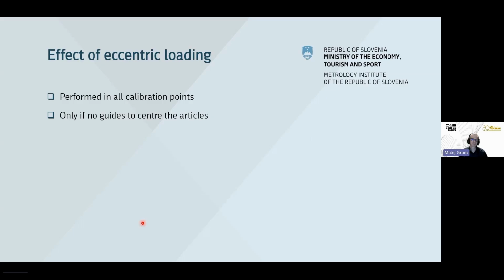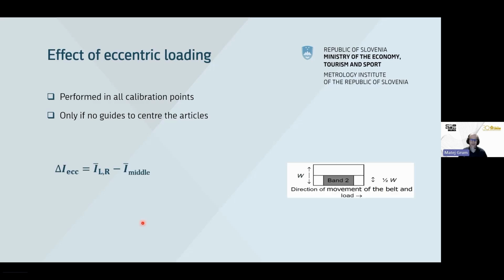The third group of measurements is done in order to evaluate the effect of eccentric loading. Again, these measurements are performed in all calibration points, but are necessary only if there are no guides to center the articles. If there are no guides to center the articles, one set of measurements is done, first of all, in the middle of the load transportation system, then on, let's say, the right hand side, and then on the left hand side. And the largest difference between the middle and the left or right hand side is taken into account for evaluation of the effect of eccentricity.